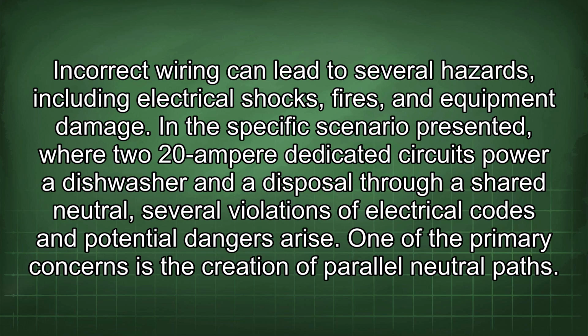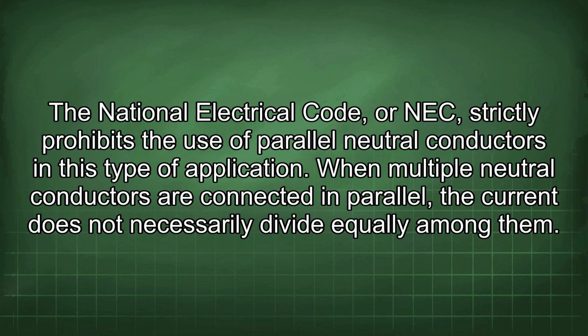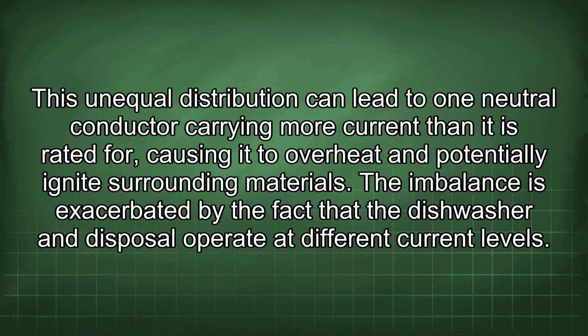In this specific scenario presented, where two 20-ampere dedicated circuits power a dishwasher and the disposal through a shared neutral, several violations of electrical codes and potential dangers arise. One of the primary concerns is the creation of parallel neutral paths. The National Electrical Code, or NEC, strictly prohibits the use of parallel neutral conductors in this type of application. When multiple neutral conductors are connected in parallel, the current does not necessarily divide equally among them. This unequal distribution can lead to one neutral conductor carrying more current than it is rated for, causing it to overheat and potentially ignite surrounding materials.